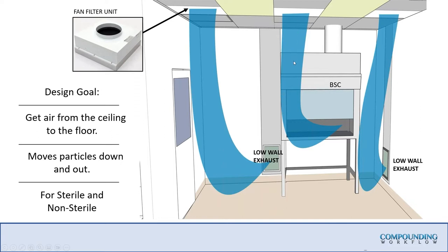There is a carve-out that says if you use a ceiling return or ceiling exhaust, you must prove it with a smoke study. From talking to colleagues in the certification business, you'll never achieve that — and that's part of the lawsuit mentioned earlier, where low walls were not integrated, there's no dilution, they can't pass a smoke study.